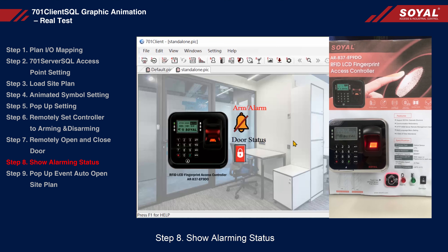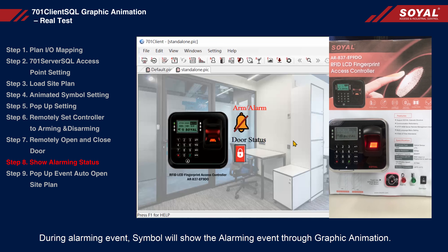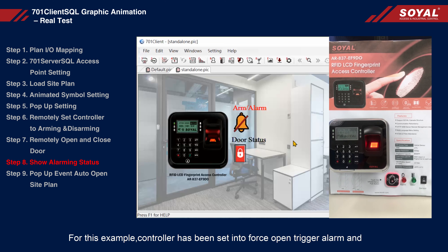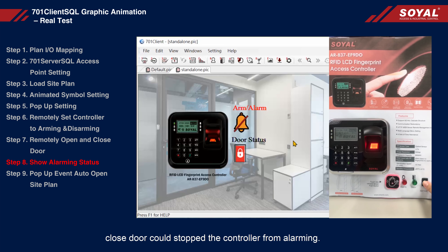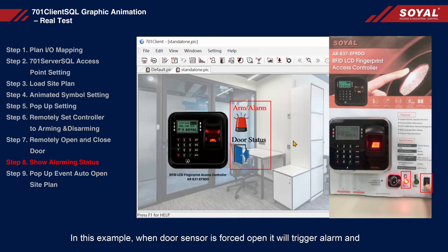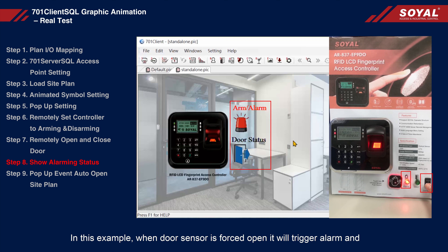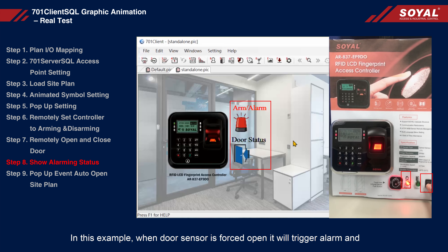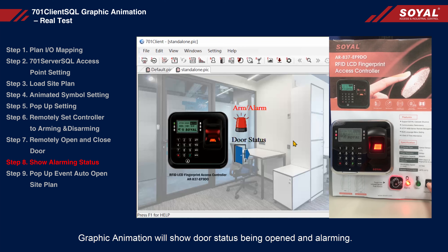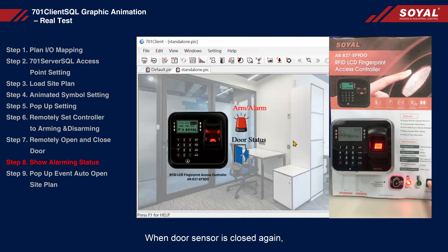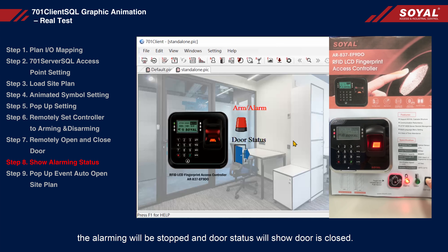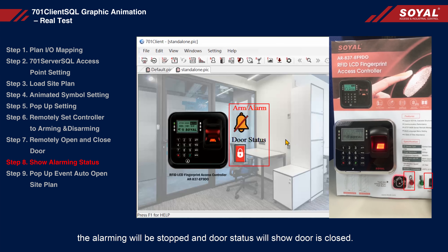Step 8: Show alarming status. During an alarming event, the symbol will show the alarming event through graphic animation. For this example, the controller has been set to trigger alarm on force open, and closing the door could stop the controller from alarming. When the door sensor is force-opened, it will trigger the alarm and the graphic animation will show door status as open and alarming. When the door is closed again, the alarming will stop and door status will show the door is closed.